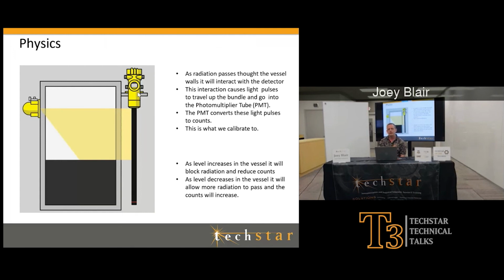Everything is going to react with the radiation. Okay, so everything is attenuated. So your vessel wall, the thickness of that vessel wall is going to have a certain attenuation factor to it. The vapor space or the air has a certain attenuation factor to it. How far away the detector is from the source all depends on how much radiation is actually passing through, and then the level of the actual product itself.